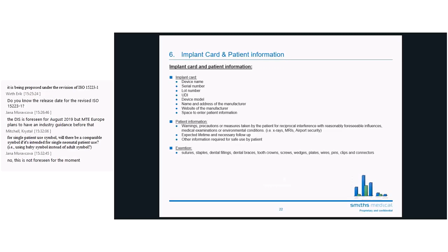So when we bring an example here, what is required, for example, for safe use, limitations of activities when people have implants, like when they have knee implants or when they have cardiovascular implants. So keep that in mind. That's to be shared and that's to be provided to the patient at the end of the day. And going back and closing the loop, to be mirrored as well in the instructions for use. What is exempted from that implant card approach is for sure the usual suspects that are listed in various sections of the MDR. So sutures, staples, dental fillings, braces, crowns, and so on. That's a common set of devices that do not need to fulfill those requirements. All right, let's move on.